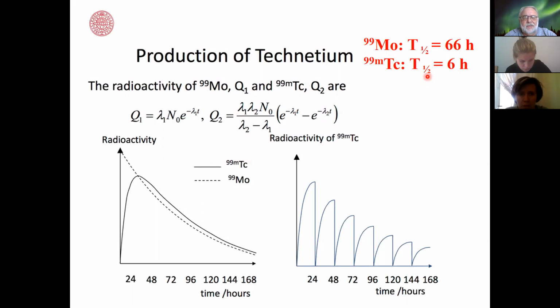So standard name of collimator for technetium and gamma cameras is low energy, high resolution collimator. It also does not generate many conversion or Auger electrons, which means that local dose for technetium-based radiopharmaceuticals is very low, very benign. We can have a look later on.